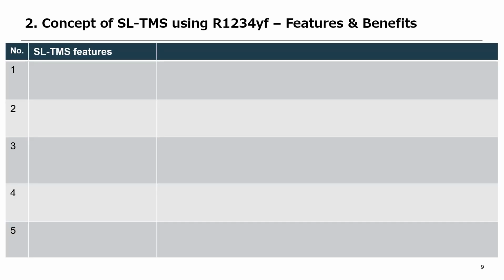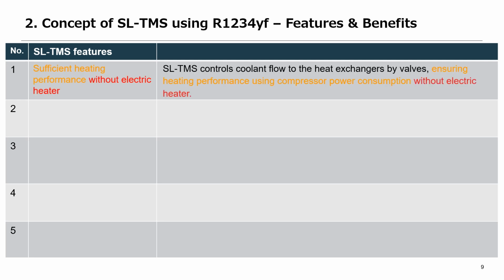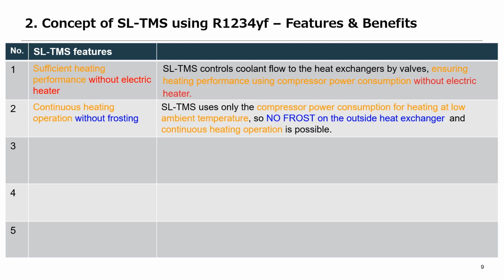This slide highlights the 5 key features and benefits of SLTMS. Sufficient heating performance without electric heater. Through precise control of coolant flow to heat exchangers via valves, SLTMS achieves robust heating using only compressor power consumption, eliminating the need for an electric heater. Continuous heating operation without frosting. By relying solely on compressor power at colder ambient temperatures, SLTMS prevents frosting of the outside heat exchanger, ensuring uninterrupted heating.